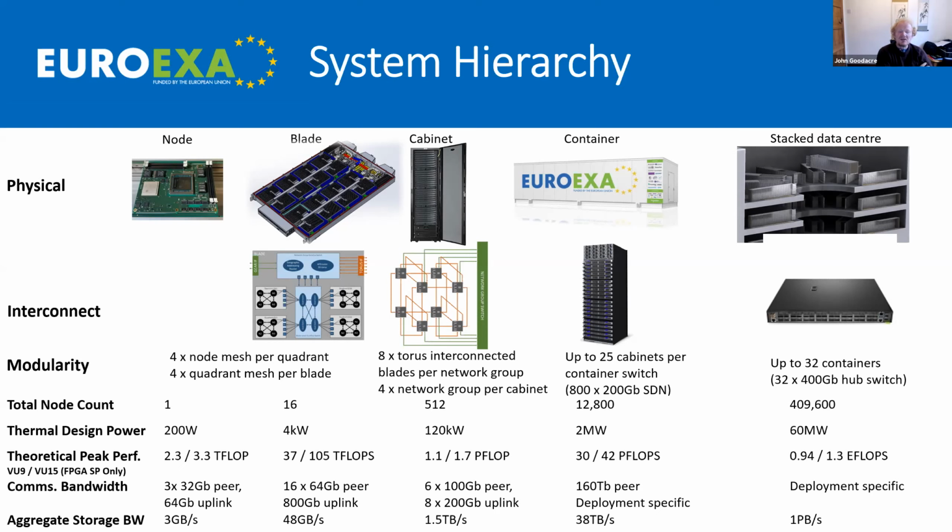We're then up to the traditional cabinet level deployment. Obviously cabinets are the things that get shipped around typically when you want some more capability. So again, we see a union here of the topology and the cooling to be able to get the density up significantly. I was looking to deploy some prototype nodes, or not prototypes, sorry, emulation nodes previously, and the host said, I've got 8 kilowatts per rack. Okay, it's not unheard of that they are still single digit. State of the art might be pushing that to 40. We're up over 100 kilowatts per rack at this point.